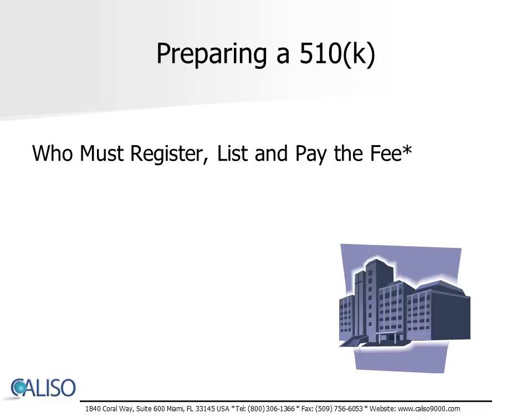You must register and list your device. The link, Who Must Register, List, and Pay the Fee, will be very helpful to determine if you must register and list. If your device requires pre-market notification clearance or approval, you will have to wait until your pre-market submission is cleared or approved to register your establishment and list the device.